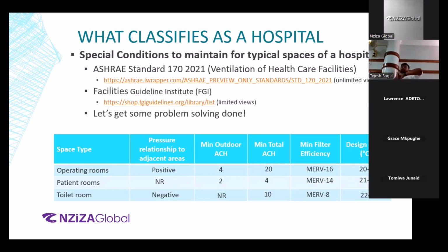So how many air changes per hour do we need? We have a formula for that. We'll go into the formula as well. But that basically means how much air change we need from the outdoor air into the indoor air. Does that make sense? Why we need it? To keep a check on the CO2 levels in the room. If we have too much CO2 build up in the room, it will lead to dizziness, sleepiness, drowsiness, and so on and so forth. Right?